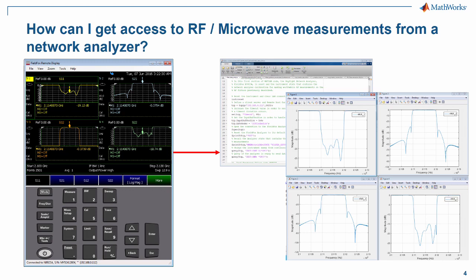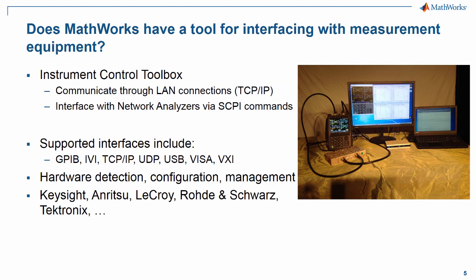I have a MATLAB script file that I use to get the data and generate MATLAB figures showing data from each of the four traces. The easiest way to interface MATLAB with measurement equipment is through a MATLAB add-on called Instrument Control Toolbox. This allows you to easily interface with vector network analyzers using a combination of MATLAB functions and SCPI commands. The Toolbox supports a number of different protocols including TCP/IP, GPIB, and USB interfaces, and it supports many network analyzer manufacturers, though today we will be highlighting use of a Keysight network analyzer.